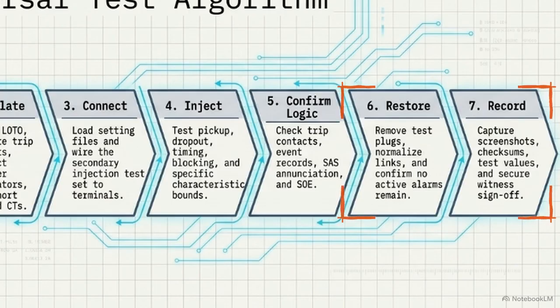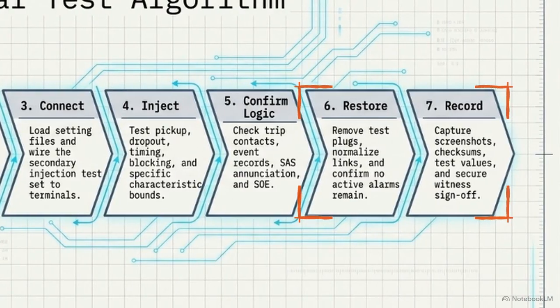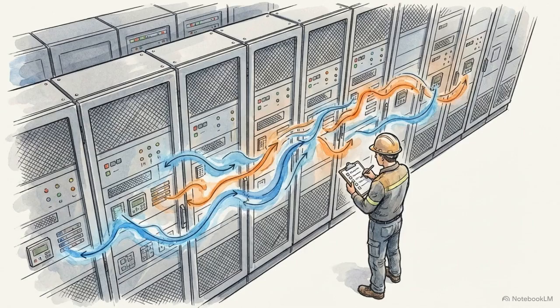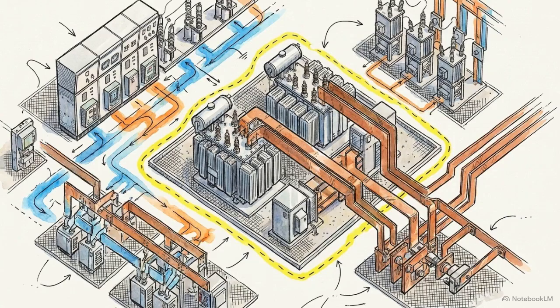Finally, steps 6 and 7 execute restoration and recording. The team removes the test blocks, normalizes the physical shorting links, confirms no active alarms remain, and captures all final test values for formal witness sign-off. This uniform 7-step protocol serves as the operational engine for the commissioning process, ensuring absolute repeatability and safety across all 41 distinct protection schemes.